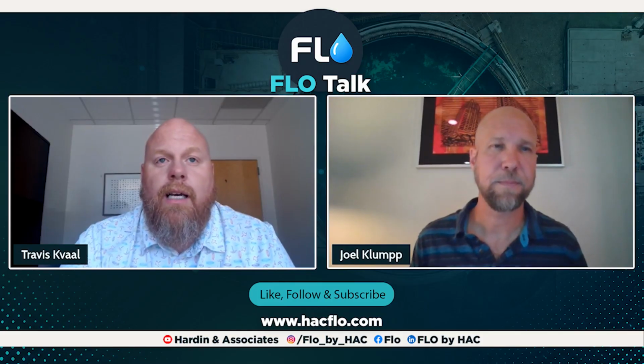Yeah, absolutely. One, somebody needs to be minding the store, right? Somebody needs to be looking at those test and maintenance reports who can interpret them, right? Who can see, hey, this assembly failed or this assembly passed. And when you get that test report in, communication with your testers is very important, right? There's a lot of places that in their ordinance, a tester might have 10 days to turn in a test report. And so if you get that test report on a health hazard and it failed 10 days ago, you've got an alarm bell ringing.